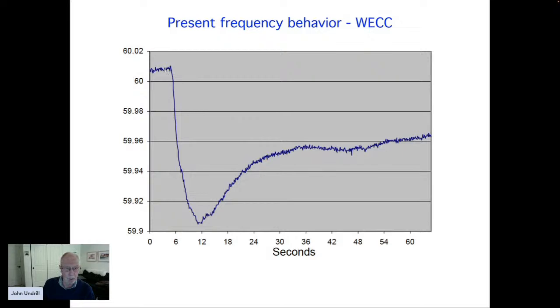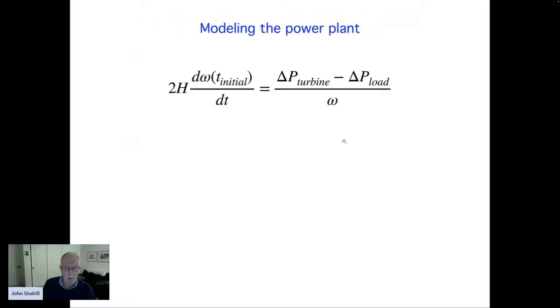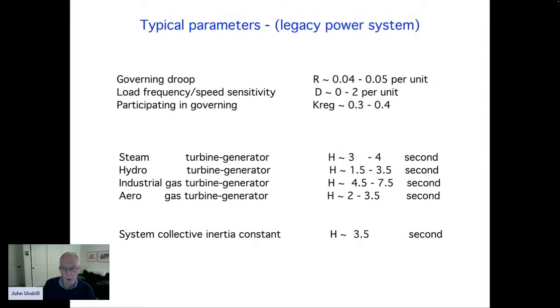This is an event that occurred when basically an 800 megawatt generator tripped off the grid when the load on the grid was about 100,000 megawatts. Frequency went down by 1/10 of a hertz and recovered decisively and settled out according to the droop equation. That's a test recording. The parameters that were used are in.